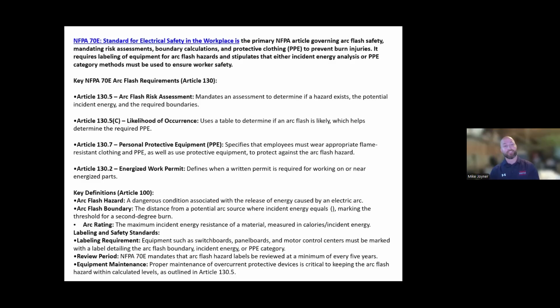Absolutely. So, with the short circuit coordination study and the arc flash requirements, the timeline, I should say, is that an electrical company would come on site and dissect the building's electrical components, starting from the outdoor pad mount transformers all the way into the switchgear, branch panels, circuit breakers, disconnects, transformers, VFDs. All of this has to be captured and sent to be engineered properly, where they do their calculations to come up with a proper PPE cal rating for each piece of electrical equipment.